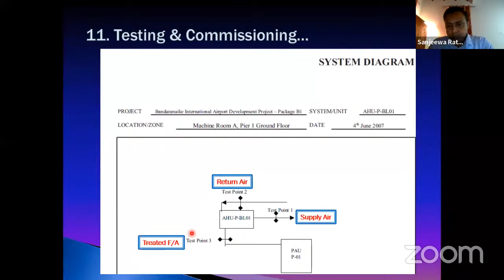Actually, the third party inspection is just to verify the performance of the equipment, not to review the design. So at the third party inspection, it's just to verify that the selected equipment performs properly. So here we took up the schematic diagram. I think you can see the AHU is numbered here, and to check the air performance, you consider the supply air here, test point 1, test point 2 is for the return air, and number 3 is the treated fresh air from this primary air unit.